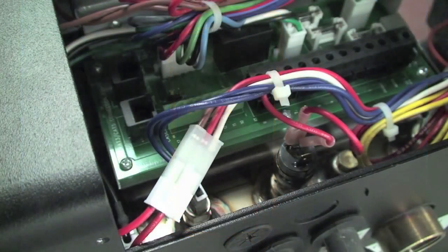Set your electrical meter to ohms value and measure the resistance by disconnecting the Molex connector from the sensor, then put your two wire leads from your meter into the sensor connector. Make sure to put your meter leads into the two pins on the connector that correspond to the blue wires.